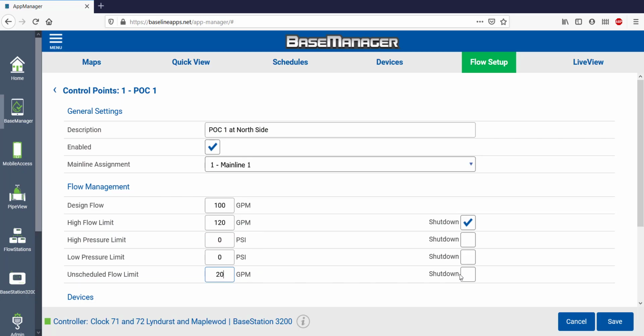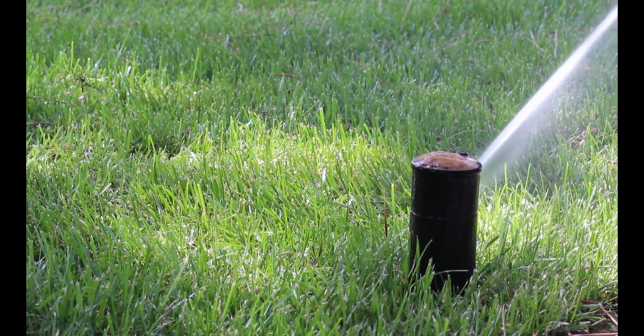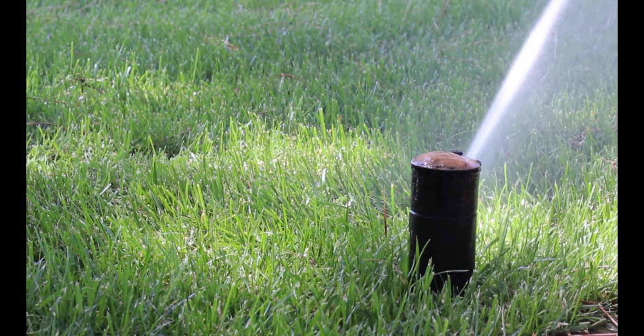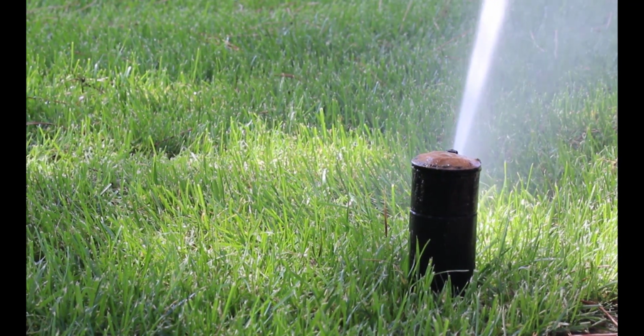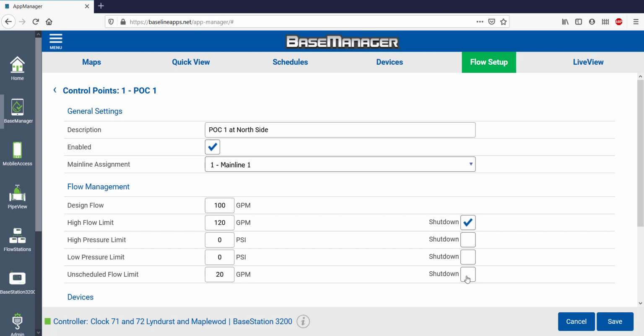Unscheduled flow is flow that runs without the controller knowing about it. An example is someone using a quick coupler or manually bleeding a valve. Both pull water from the mainline without the controller knowing about it. I decided not to select shutdown, so anytime someone uses more than 20 GPM of water, I'll get an alert, but it won't shut down.